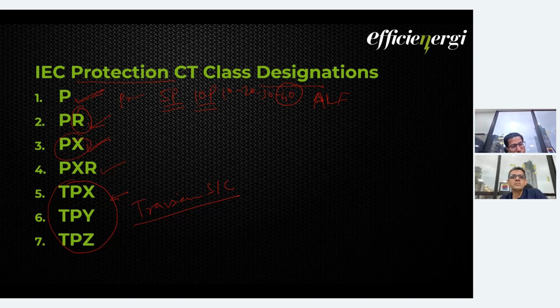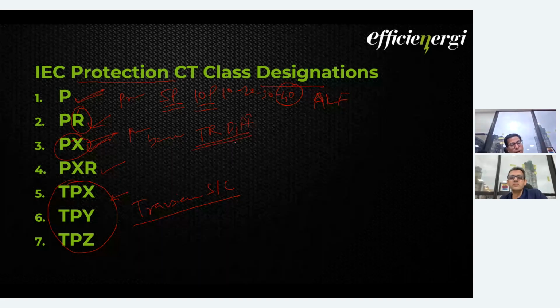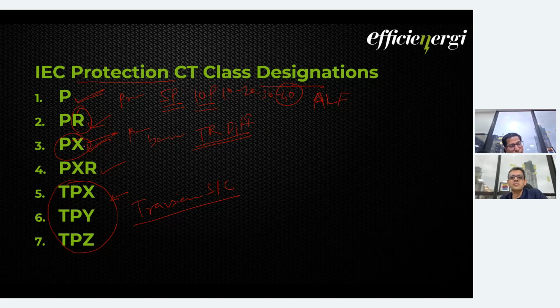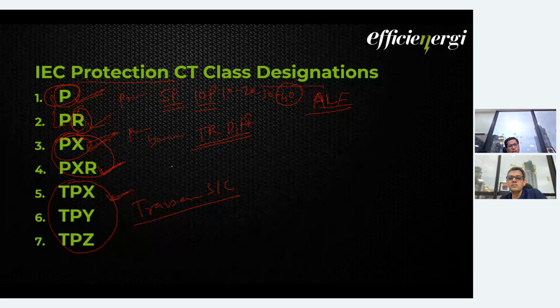PX CT is also for protection, but for this class of CTs, everything is properly defined, and these CTs are to be designed based on the requirements of the protection. So if it is a transformer differential, then you must know the requirement. Here the remanence is not taken care of because R is not there. So this is PR. So PXR, here the remanence is also taken care of. So these two CT classes are basically used for unit protection, where the saturation is properly defined. Here we know the ALF and we can go ahead with this ALF. We know the remanence, we can go ahead with these PR CTs. But normally you will see the P CT everywhere. Again, this is for transient performance CTs. So this is the designation classes for IEC protection CTs.